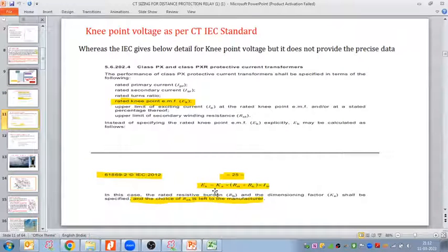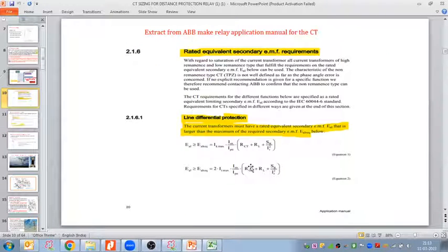But as I told yesterday, the best method, or I can say the correct method, is to follow the formula given in the relay application manual, because each relay has a different knee point voltage or voltage requirement. Even within a single company, suppose you are using an ABB make relay, if you change the model, say you are using RED670, or REL670, or REB500 relay which we use for busbar protection, then in a single manufacturer different relay models have different CT knee point voltage requirements.